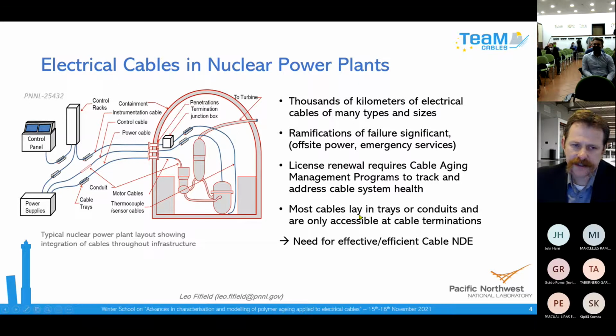So as plants, as I mentioned, they were licensed for 40 years. As they've received license renewal to operate for longer, plants have had to institute what we call cable aging management programs, or CAMPs, to make sure that the cables that are decades old continue to operate reliably. And so these cable aging management programs have to inventory the cables and understand which cables are at risk of outliving their useful life, what their status is, how often they need to be tested, how to be tested, and what situations they're in.